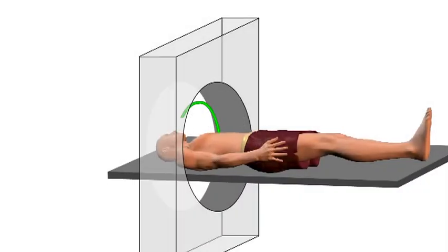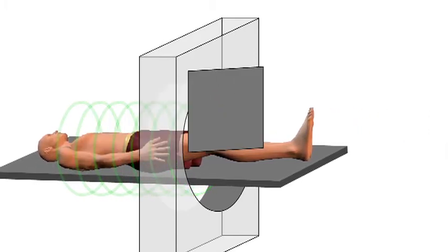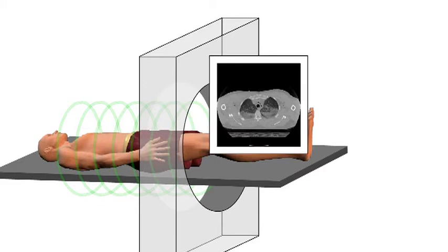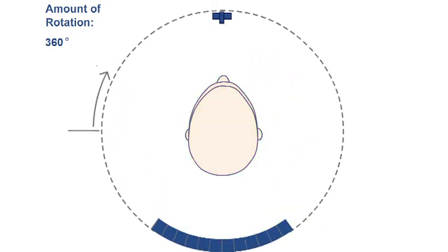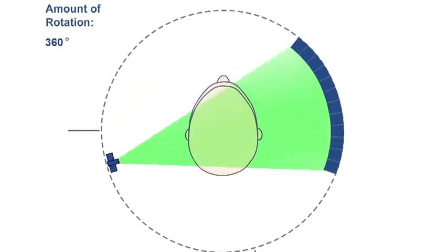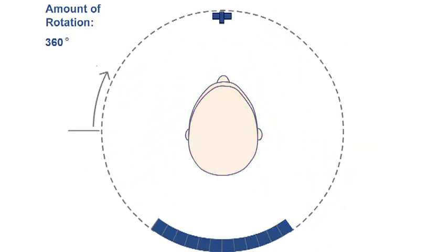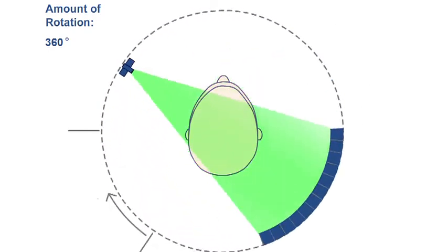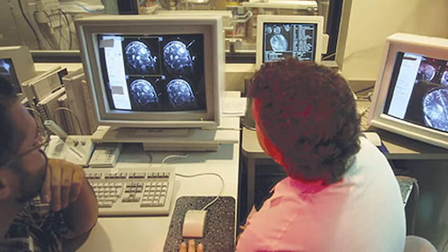Modern helical or spiral CT units are constructed using slip ring technology that allows the X-ray tube to rotate 360 degrees around the patient as the table moves through the gantry. A helical unit can complete an entire dynamic study in less than 1 minute, but the primary beam is on the entire time. Because of the continuous exposure of the beam, patient dose in CT can be significantly higher than in radiography. For occupational dose, however, it is generally the opposite. Most CT technologists receive little or no radiation exposure because they are usually behind the secondary barrier of the control room wall while the beam is on.